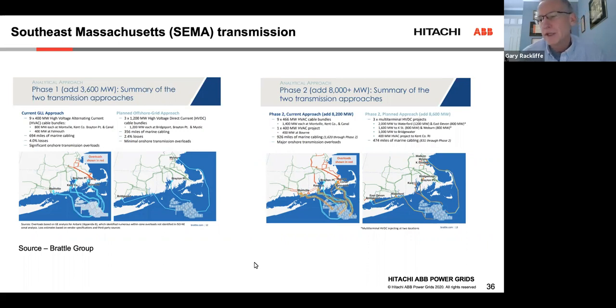The benefit of HVDC cables is you can use two cables and move about 1.2 gigawatts of power. AC cables require three cables, and you can move about 400 megawatts of power. So HVDC cables, when you're looking at landing points, give you a little bit more efficiency in terms of the number of landing points required, because you can move a lot more power through two HVDC cables than you can through three AC cables.